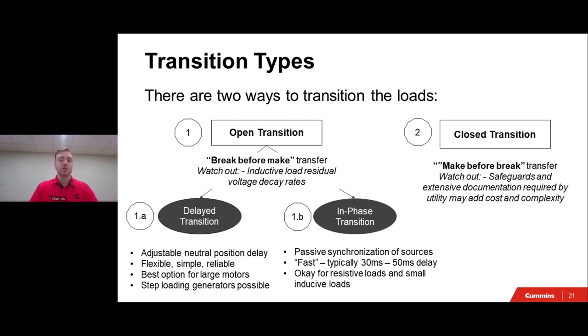So what is a closed transition? Like I said, with open, it's a break before you make. However, the closed is a make before you break style of transfer, and the transfer switch will make a connection to the new power source before breaking its connection to the old one. This means that there is no gap between disconnection and connection. The downstream loads will receive continuous power throughout the transfer process. Switches configured for closed transitions usually transfer power automatically as soon as both sources are closely synchronized in phase, voltage, and frequency. The overlap period during which both sources are simultaneously connected or paralleled usually lasts no more than 100 milliseconds. Because of this, utilities may mandate additional safeguards, which could add additional cost to your systems.